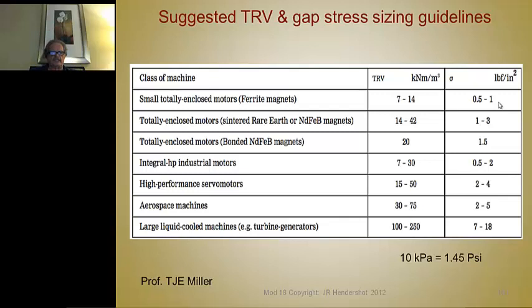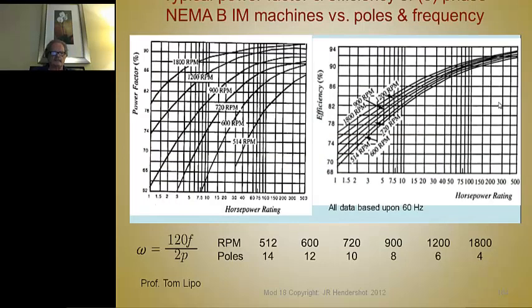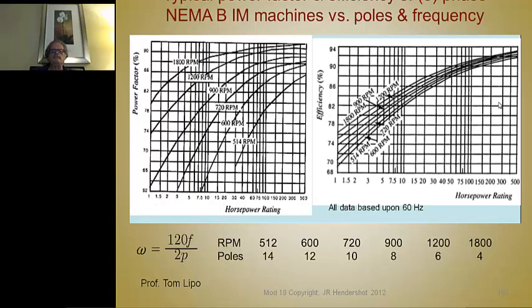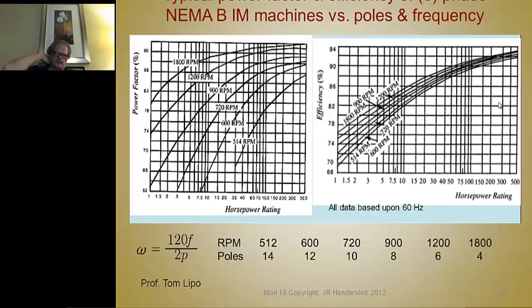Here's the repeated list of suggested torque per rotor volume and gap stress sizing guidelines. You can decide which enclosure you're going to have and shoot for one of these for sizing purposes. Here's also some material developed by Professor Tom Lipo at the University of Wisconsin, which gives expected power factors for different horsepower ratings and number of poles. Number of poles relates to frequency in accordance with the formula shown, and the plot on the right allows you to select goals for efficiency. These are all based on 60 hertz, but still good for comparison purposes.